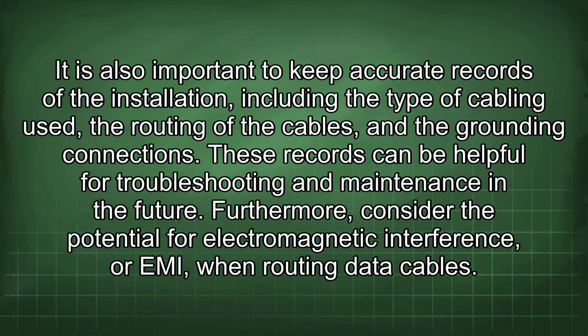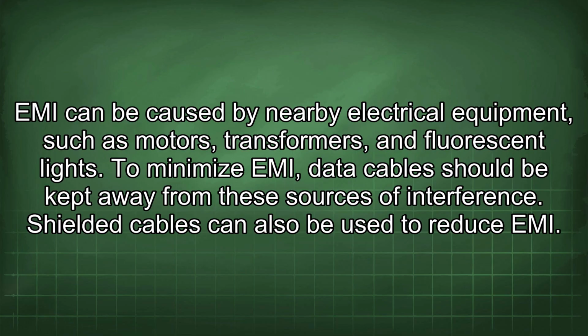It is also important to keep accurate records of the installation, including the type of cabling used, the routing of the cables, and the grounding connections. These records can be helpful for troubleshooting and maintenance in the future. Furthermore, consider the potential for electromagnetic interference, or EMI, when routing data cables. EMI can be caused by nearby electrical equipment such as motors, transformers, and fluorescent lights. To minimize EMI, data cables should be kept away from these sources of interference. Shielded cables can also be used to reduce the EMI.